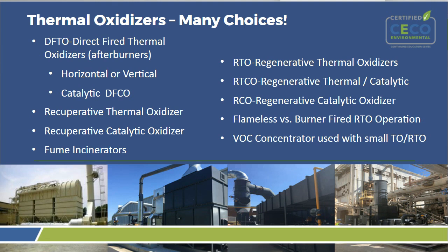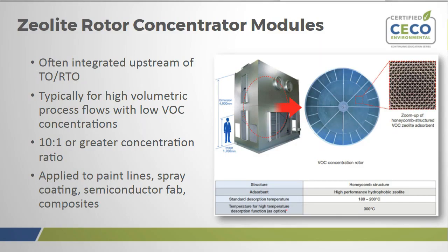We have the zeolite rotor module concentrators. We're just going to touch on these today. We could probably do a webinar on these as well, Mary. Typically, the concentrator media of choice is a zeolite rotor module, hydrophobic zeolite, and it's typically a honeycomb structured adsorbent. It adsorbs the VOCs and then it's desorbed.